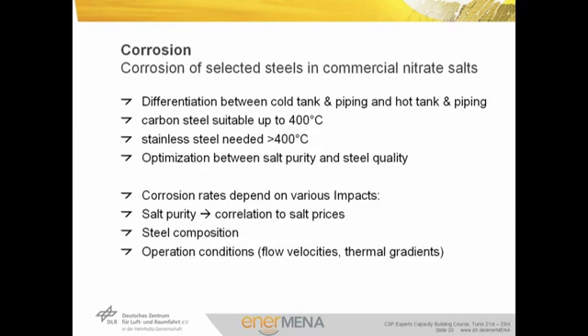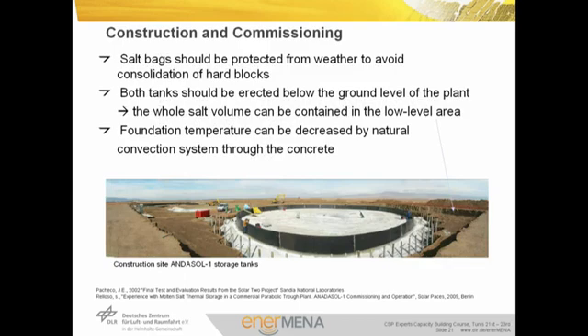Corrosion plays an important role in the design of two-tank molten salt storage systems, and detailed knowledge is important for cost-effective design. Since corrosion is strongly dependent on the molten salt temperature, the design of the cold tank is usually different from that of the hot tank. While carbon steel is suitable up to 400 degrees, stainless steel is needed for operation temperatures exceeding 400 degrees. The purity of the salt also affects the corrosion rate, and a cost optimization should be done for the qualities of both the salt and the steel. The corrosion rate is affected by many factors apart from salt purity and steel composition, and operation conditions also show a significant effect.